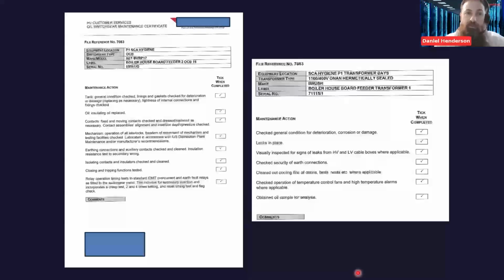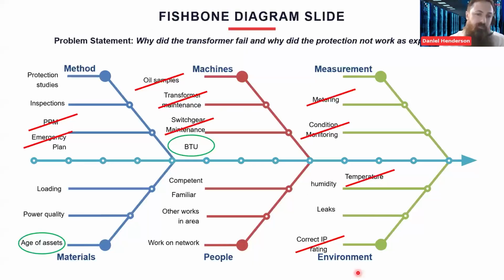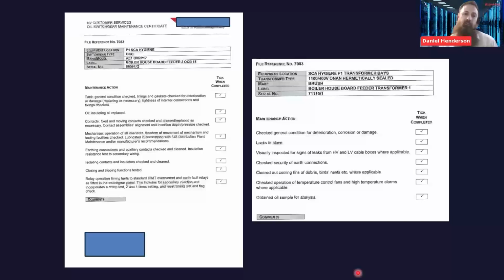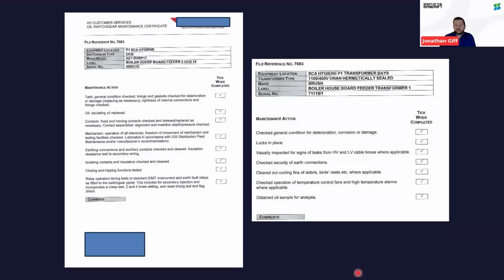Latest maintenance point, so for the circuit breaker and the transformer. Again, I know they're very generic checklists, but to go back to one of the points that was made in the chat, the actual maintenance consisted of the circuit breaker being withdrawn, mechanical maintenance and testing done on the circuit breaker, and then that circuit breaker put into the circuit earth position, so grounding that circuit, maintaining the transformer, and then on completion, an IR test from the circuit shutters down to the primary windings. So there was a 5 kV IR insulation resistance test done as part of the maintenance, which was done like the year before. And there is the certificate for the battery tripping unit.